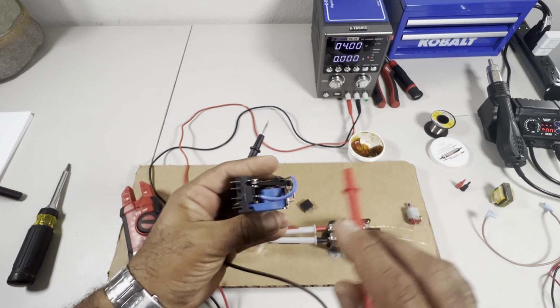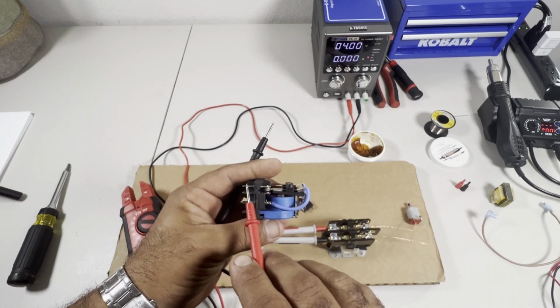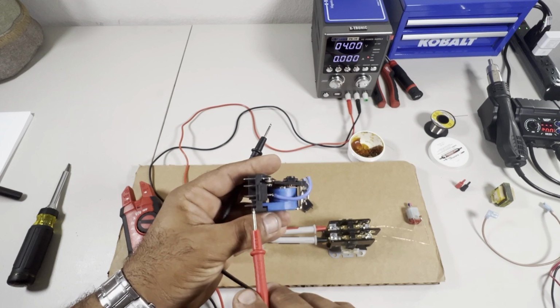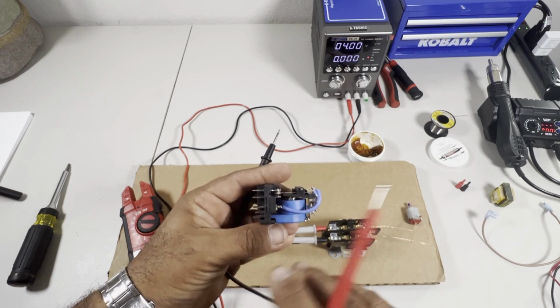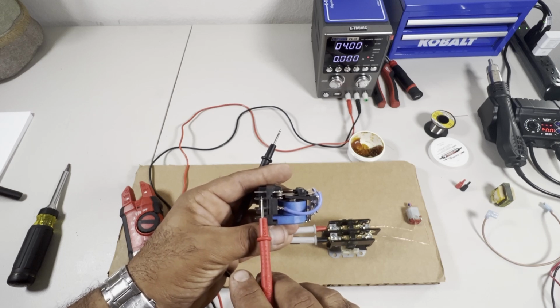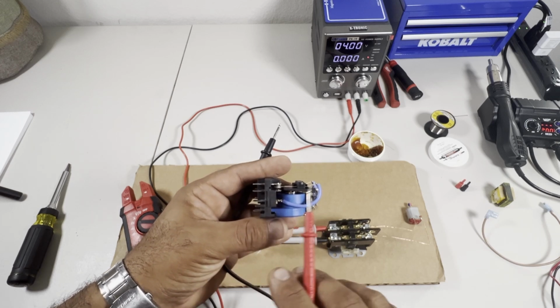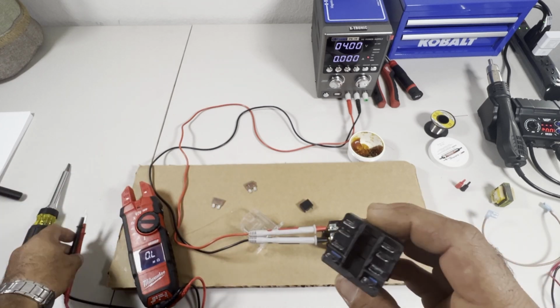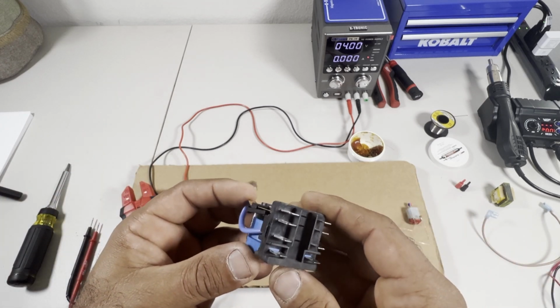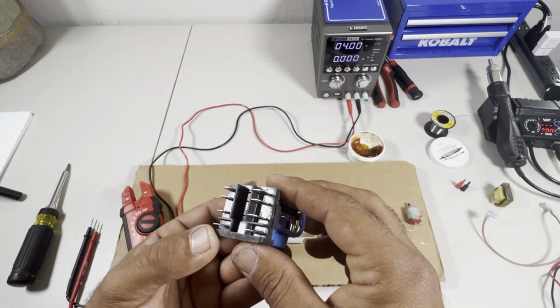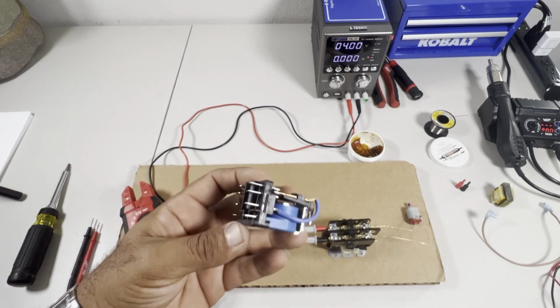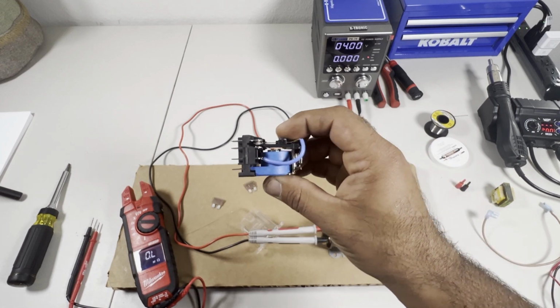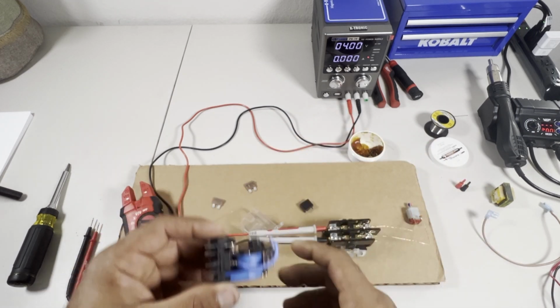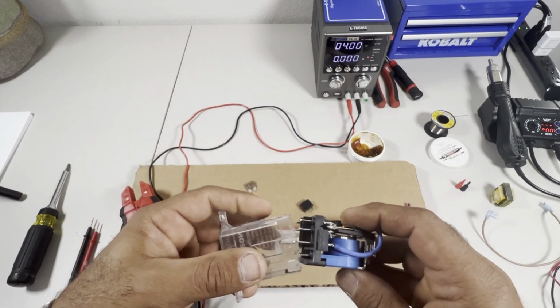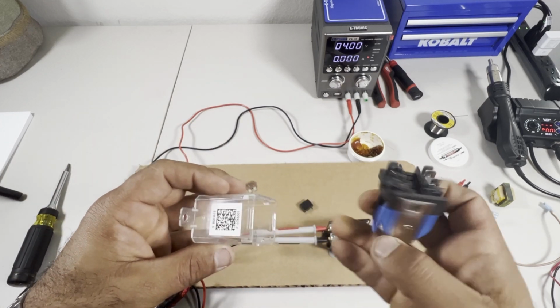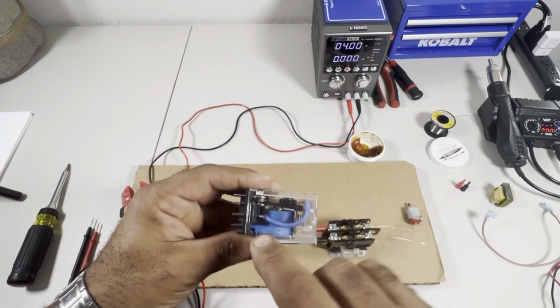Now, one more time, normally closed is the one that is closed with the common terminal when no power is applied. And normally open is the one that, again, is open when no power is applied. Some of these relays are going to have a marking on them that says normally open or normally closed. This one doesn't, so you have to either check the manufacturer specification on it, or you can see through the glass like this one and check what contacts are what.